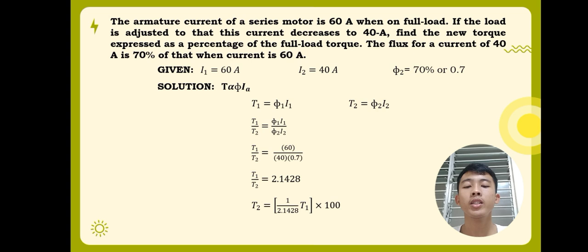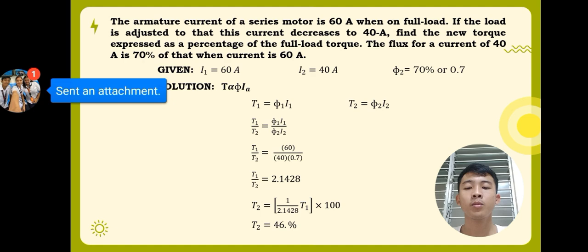Then, since what we're finding is the new torque expressed as a percentage of the full load torque, we need to manipulate these values and isolate T2, which will yield T2 is equal to 1 over 2.1428 times 100. And computing this using calculator, we can have T2 is equal to 46%. Therefore, the new torque expressed as a percentage of the full load torque is 46%. That would be all for the first problem.